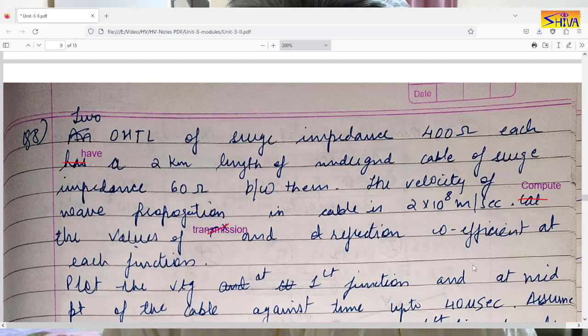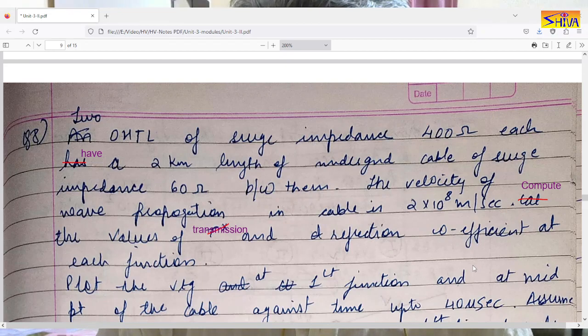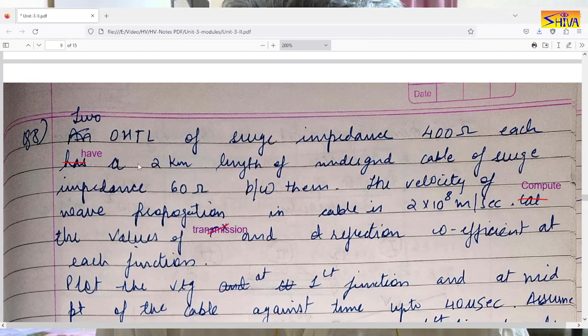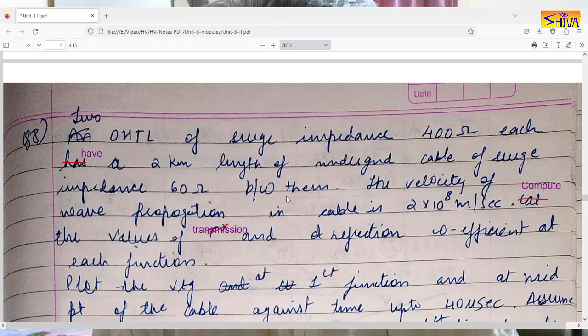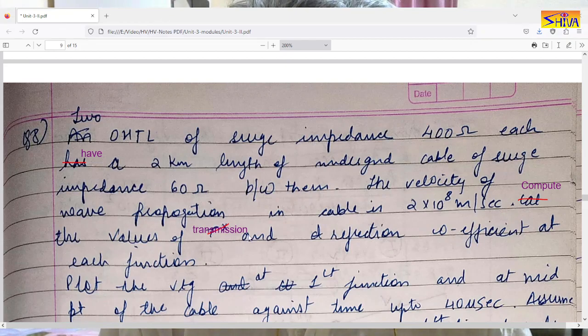Hello friends, good morning. In today's video lecture I will take a few more numericals on traveling waves. The first numerical is: two overhead transmission lines of surge impedance 400 ohms each have a two kilometer length of underground cable of surge impedance 60 ohms between them. The velocity of wave propagation in the cable is 2×10⁸ meters per second. Compute the value of transmission and reflection coefficient at each junction.